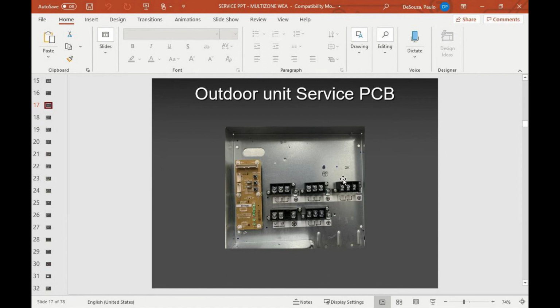So don't worry. The unit does its own oil return. Once every 8 hours, or once every 16 hours, depending on the temperature of the compressor. Okay? And that is done by the built-in software in that PCB. Okay.